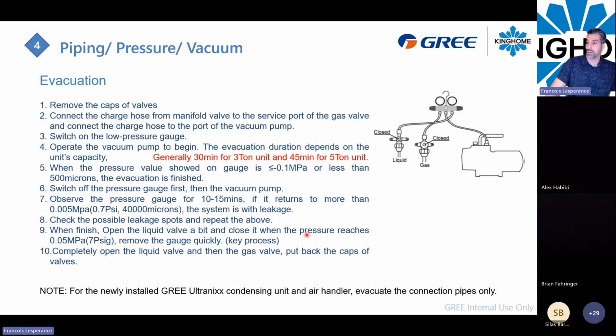When it's done, again, you will hook up the vacuum pump, so you will remove your pressure. It's really important. You can leave like 1 or 2 psi of nitrogen in the system before you start the pump, just to make sure you don't have moisture or air inside of the system. And then you will have to do 2 vacuums, one for the liquid line and one for the suction line. Then bring your micron gauge attached to the system, and bring the micron to 500 microns.